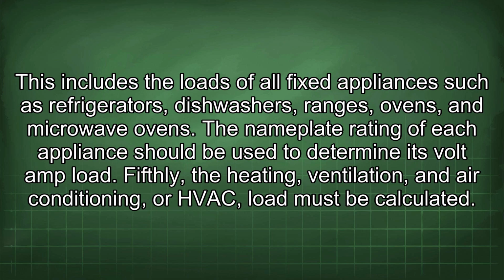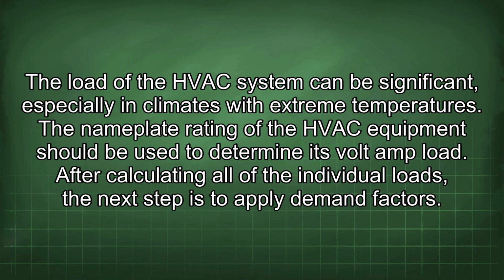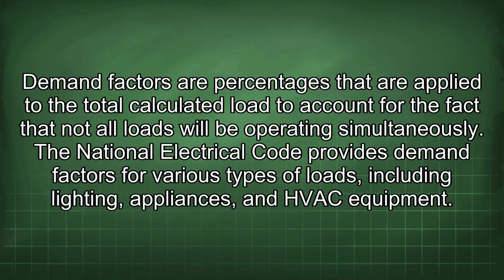Fifthly, the heating, ventilation, and air conditioning, or HVAC, load must be calculated. The load of the HVAC system can be significant, especially in climates with extreme temperatures. The nameplate rating of the HVAC equipment should be used to determine its volt-amp load. After calculating all of the individual loads, the next step is to apply demand factors. Demand factors are percentages that are applied to the total calculated load to account for the fact that not all loads will be operating simultaneously.